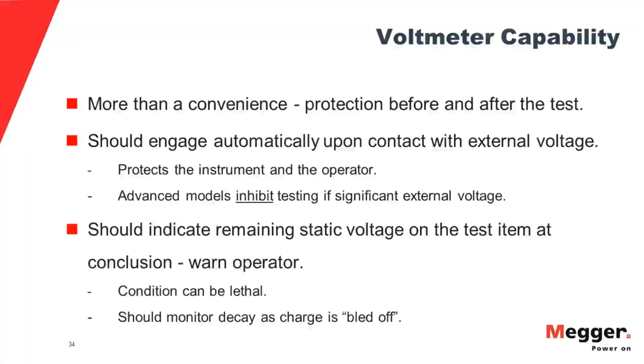First of all, insulation tests are always performed on de-energized equipment, never on live equipment, but equipment can go live for a variety of reasons. And so a good quality tester will warn you at the beginning of the test. It'll beep, it'll flash, it will let the operator know, hey, you're not on a dead circuit here. And that mainly protects the instrument. Years ago, guys would hook up, they wouldn't know what was going on, they would press the test button, and then they would cook the tester. The repair department would get insulation testers back for so-called warranty repair, and they would open them up, and there's a burn track across the board from one terminal to the other. That is not warranty repair. You put 5,000 volts or something on this, and we told you not to do that. That has all been eliminated on a good quality tester.